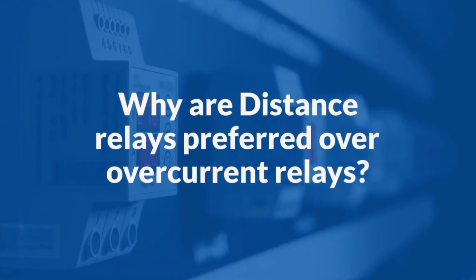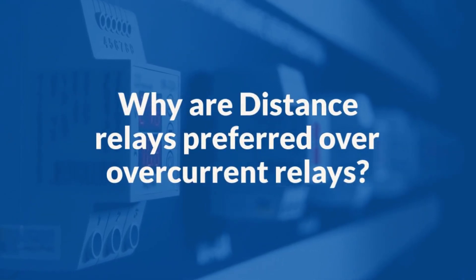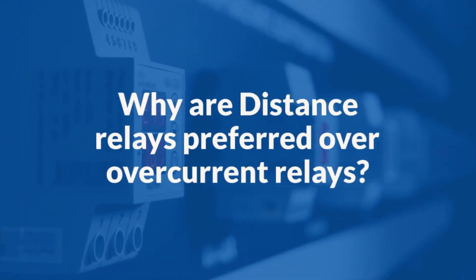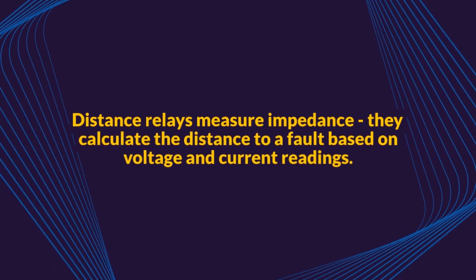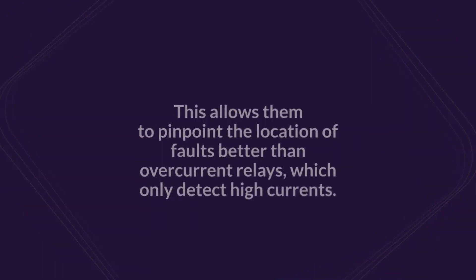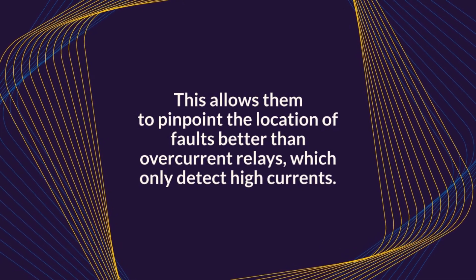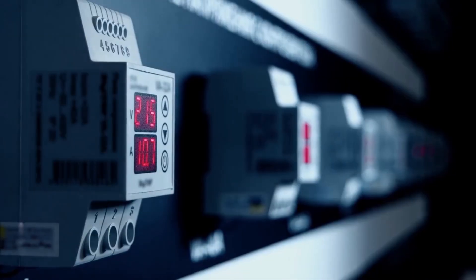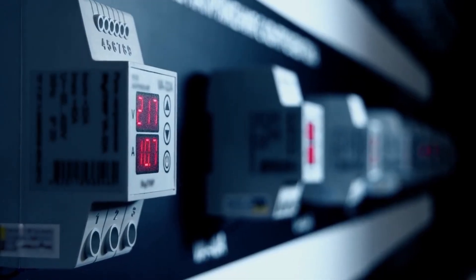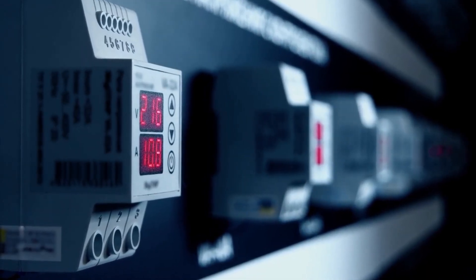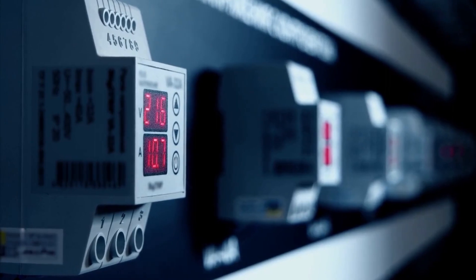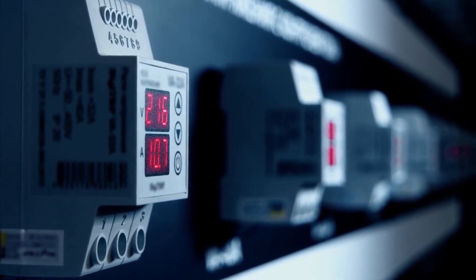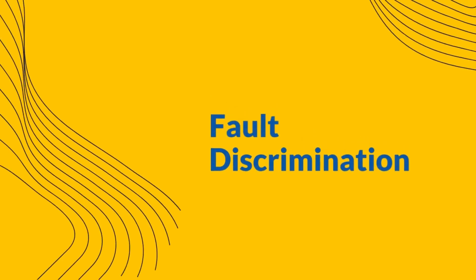Why are distance relays preferred over overcurrent relays? Distance relays measure impedance — they calculate the distance to a fault based on voltage and current readings. This allows them to pinpoint the location of faults better than overcurrent relays, which only detect high currents. Distance relays are frequently preferred over overcurrent relays for a few key reasons.